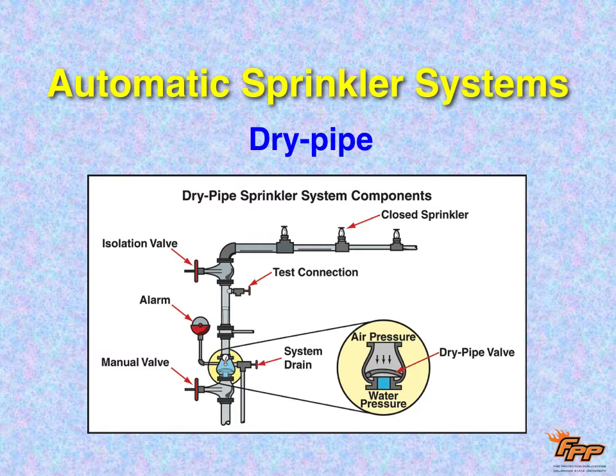What happens is one of the sprinkler heads pops because of heat, and then the cover falls off, the air comes out because it's under pressure, and as soon as the air comes out, that valve will be pushed open by the water pressure on the other side. The water will fill the whole plumbing system, but will only come out of those sprinkler heads that have popped. The downside is it's slower. So there's another kind of system called pre-action we'll talk about in a second. But first, deluge.